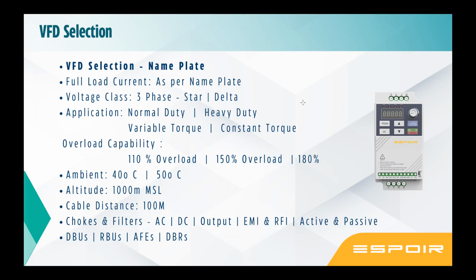Now, the other aspect of selecting a drive should be based on the ambient temperature of the environment where the drive is going to be installed. This is very, very important because if you buy a European drive, it is designed for a European standard. There, the temperature doesn't go beyond 30-35 degrees. The same thing you cannot apply here. Here in India, the average temperature at summer peak goes more than 42 degrees.